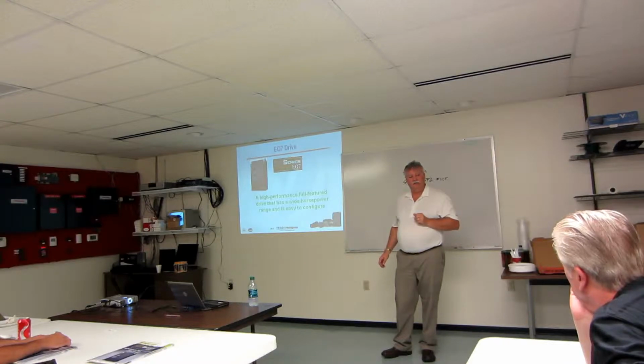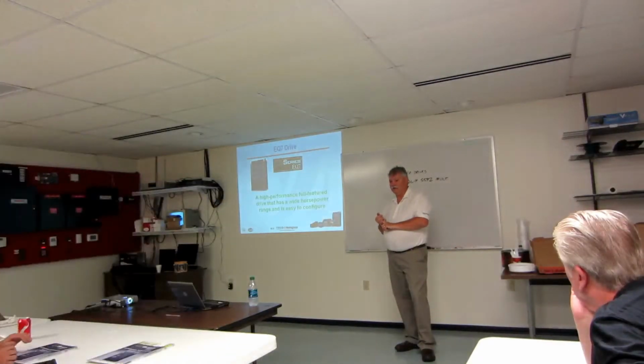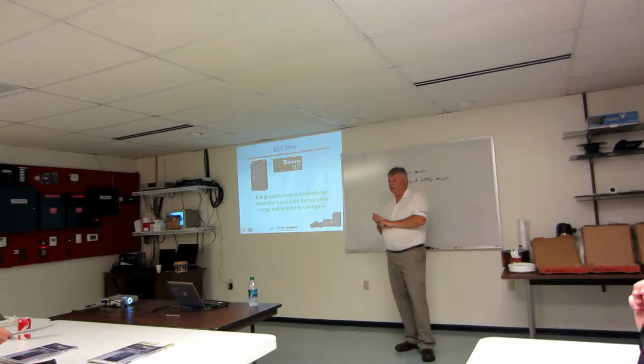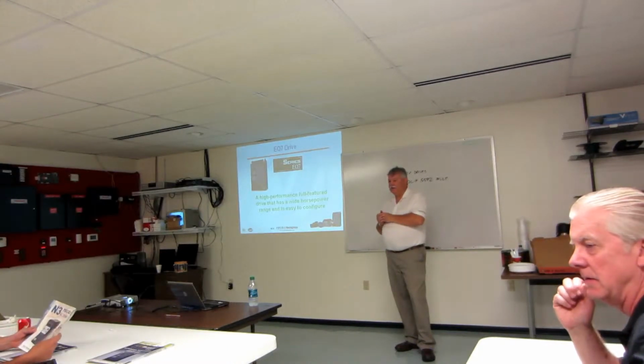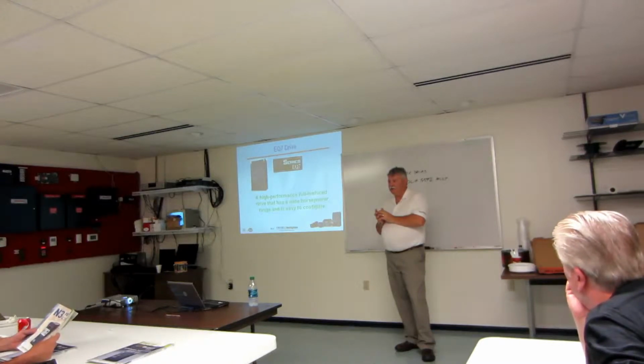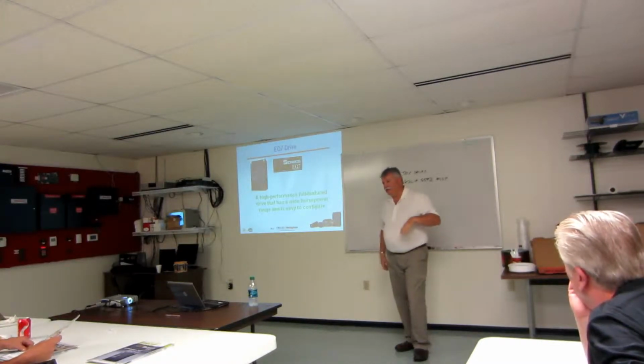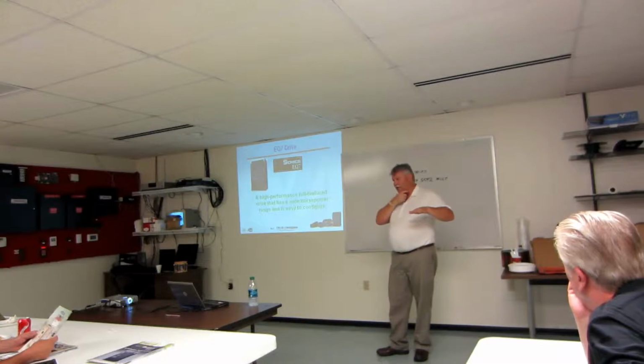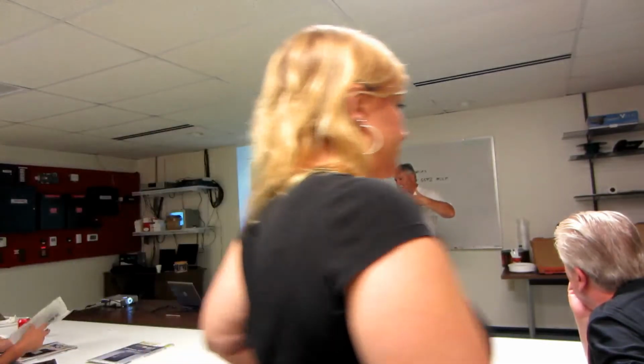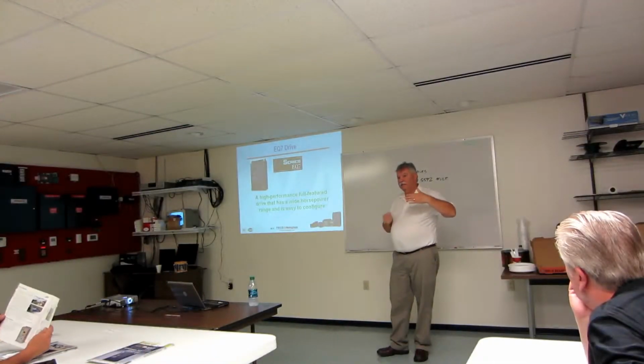It also has some features for the pump role, like we can put in engineering units. You've got that sleep wake mode. You've got the ability to detect on your feedback whether you're at a low level, so you can set a threshold level and say if I'm below this then there's a problem. Same thing with a high level.